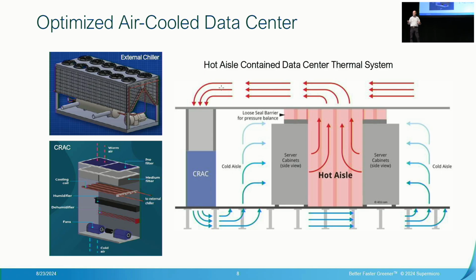There's open air, cold aisle, hot aisle. But this, or a variant of it, has emerged as one of the most efficient ways to do an air-cooled data center—really a hot air chimney or plenum, with racks rolled in from both sides.